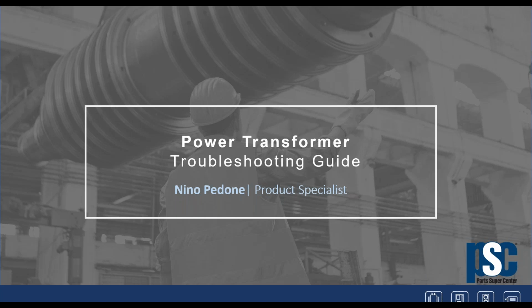Because again, on every transformer, input power and output power is almost the same. As a matter of fact, the transformer is the most efficient amongst the electrical machines, 99.8%, 99.9%. So with this being said, we start by trying to identify what could be happening inside the transformer.